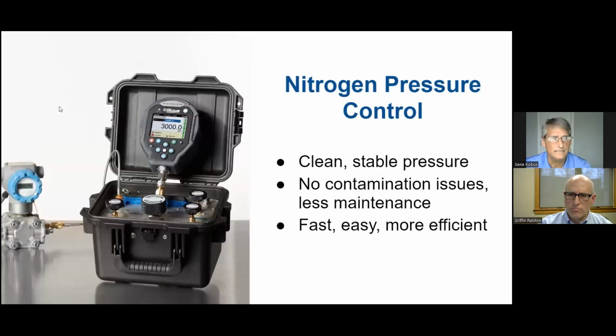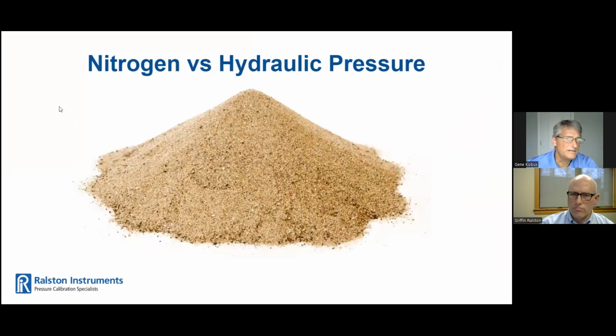A better way to calibrate transmitters, from pressure instability to contamination and maintenance downtime: nitrogen pressure control eliminates the hassle of calibrating with hydraulics and hand pumps, and gives cleaner, more efficient, and more accurate calibrations. So here's a great way to compare calibrating with hydraulic fluid to calibrating with compressed nitrogen.